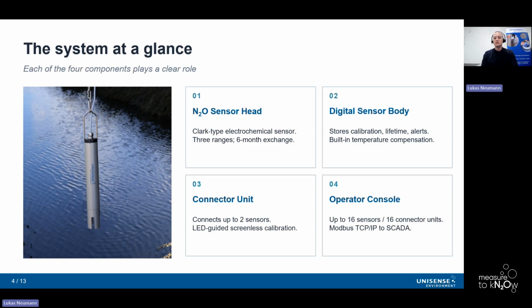First, there are 4 components now, as opposed to 3 before. The new member of the family here is the connector unit. We'll get to that just in a minute. First, we have the sensor head, the consumable item. Customers that have our previous gen system will be very familiar with this. It's a Clark type electrochemical sensor available in 3 ranges, so standard, medium, and high, and they need to be exchanged roughly every 6 months. Then we have the digital sensor body. This is where a big change sits. It houses the digital amplifier, temperature sensor, and the EEPROM that stores all the calibration history. Then we have the connector unit, which connects up to 2 sensors and mounts very close to the tank.